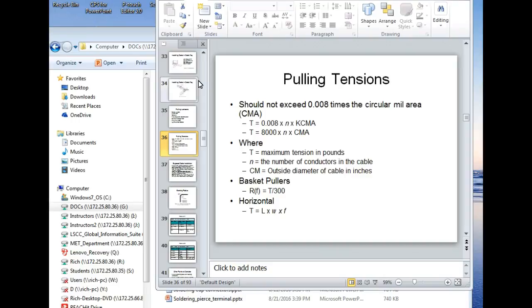So here we go. What we do is take a cable, the tension would be equal to a constant, 0.008, times the KC mils. So let's say I was going to pull a cable that contained 20 conductors, write this down, required 20, 14 gauge conductor.